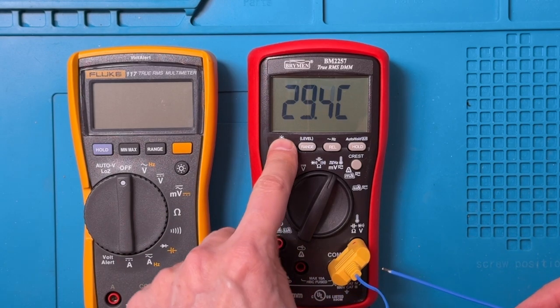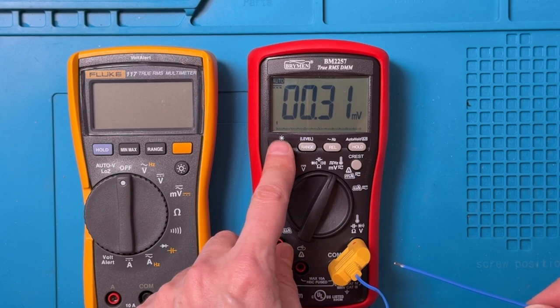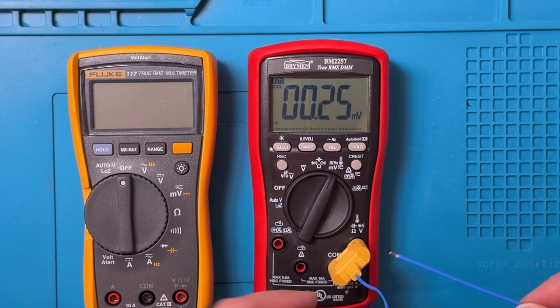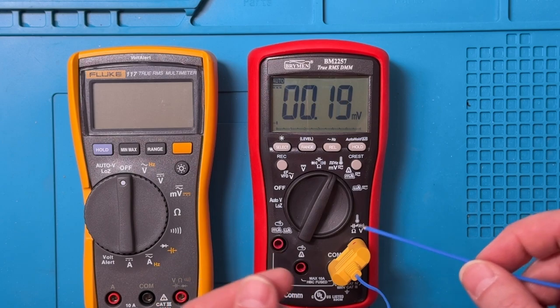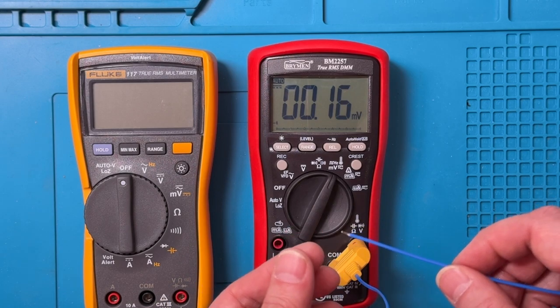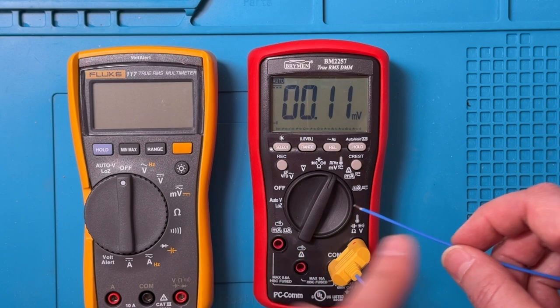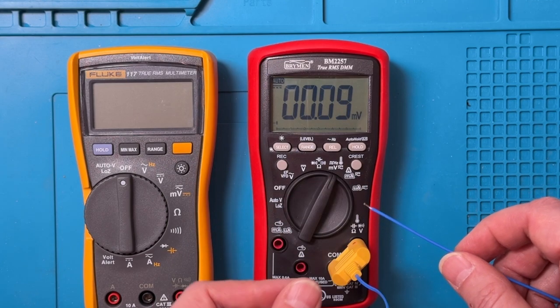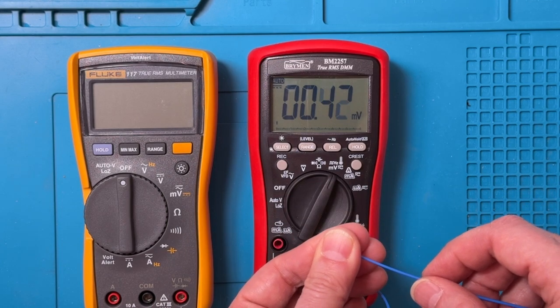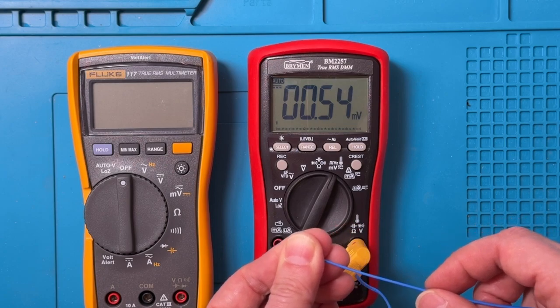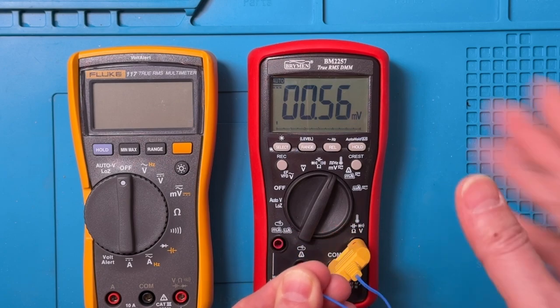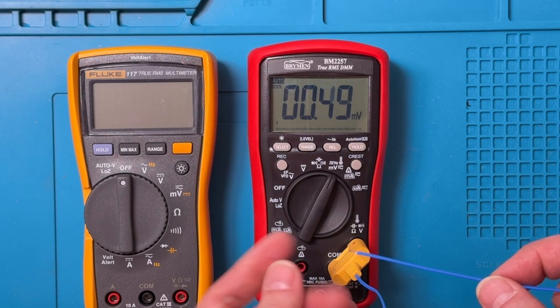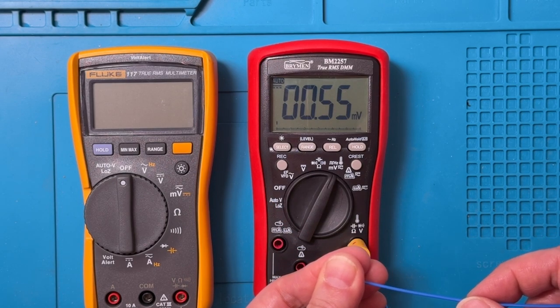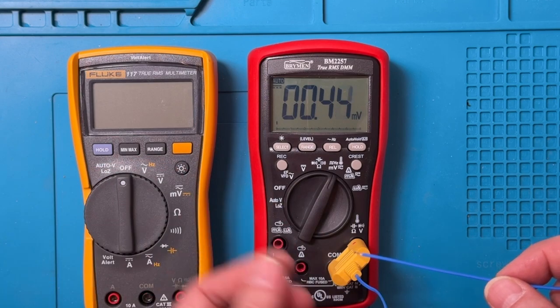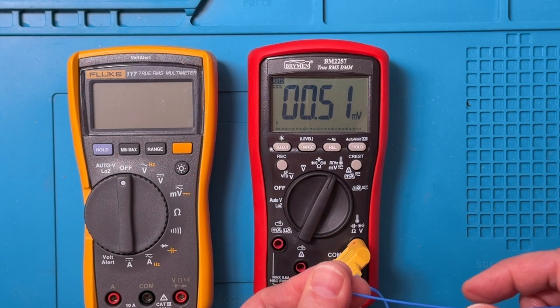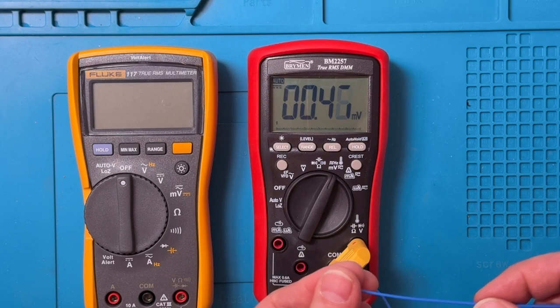And in case you're really curious, well, there's a Fahrenheit mode, but the thermocouple puts out a millivolt value, and as the temperature rises, the millivolt level increases. So right now, as it's cooling off, you can see that it's dropping down. If I touch it, you can see that the millivolt level rises quite rapidly. And so there's some internal calibration where it knows what millivolt level corresponds to a certain temperature. So that's how the temperature measurement works.